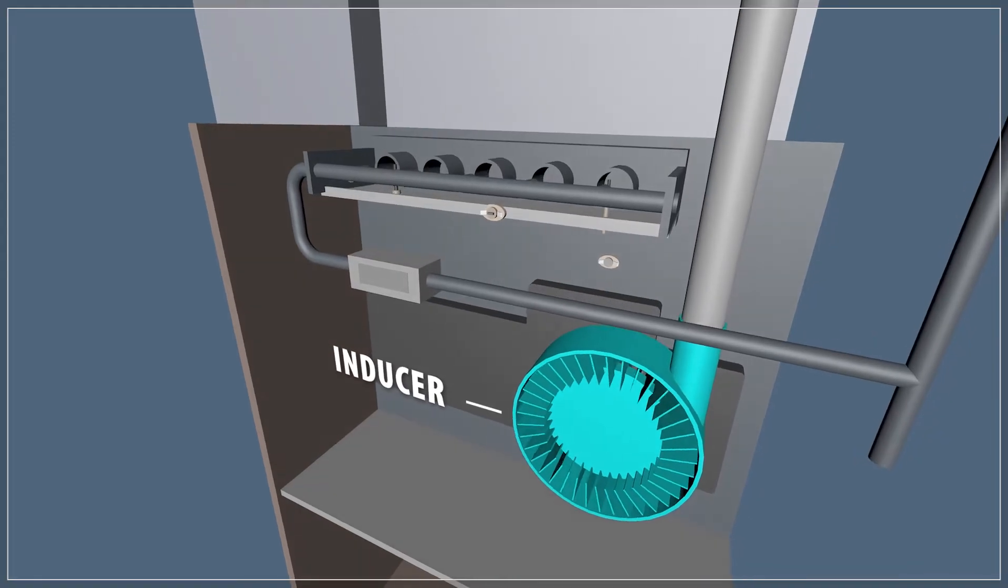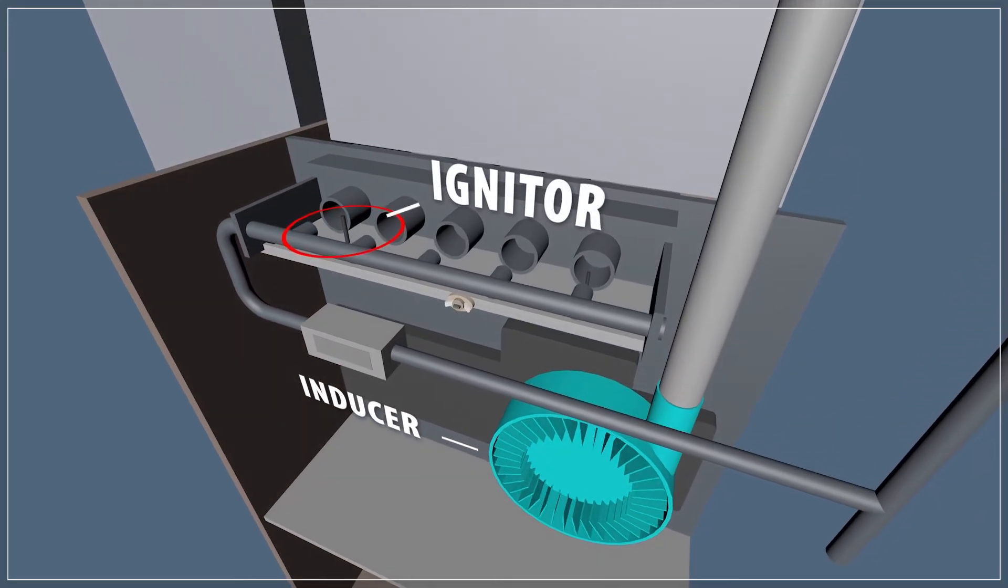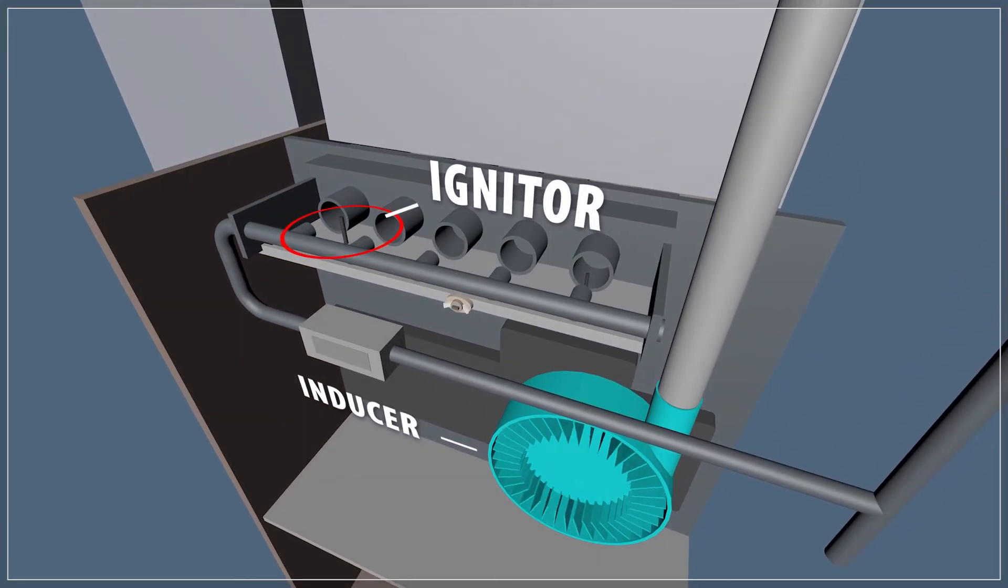If the inducer motor runs but the igniter doesn't glow, then it's best to test the igniter for continuity before replacing.